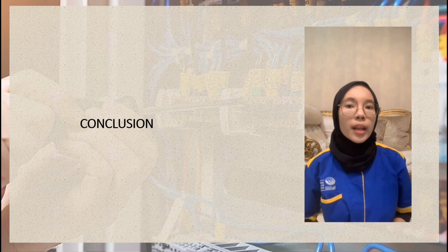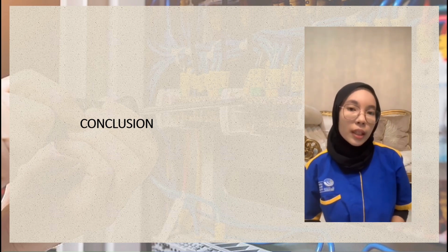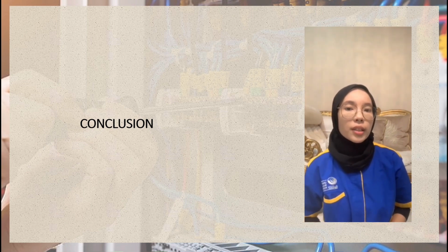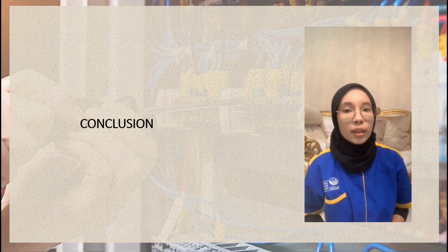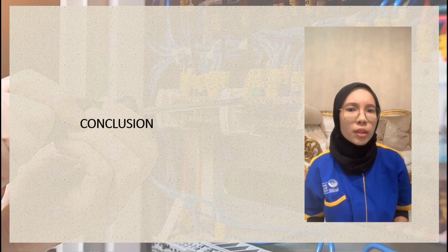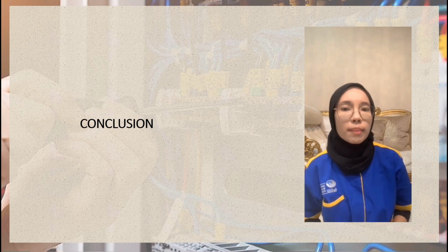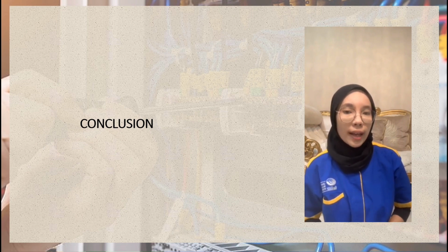Each building or department has its criteria that we need to follow by using the JKR standard guideline. This guideline, also known as the Public Works Department JKR standard, provides guidelines for lighting design and requirements for various interior spaces and buildings, including stairs. In this assignment, we can see some buildings require different luminaires, such as offices and corridors, which have different luminaire values due to the operation in that area. Most have varying ceiling heights in each room, hence the lighting arrangement depends substantially on the room's height.